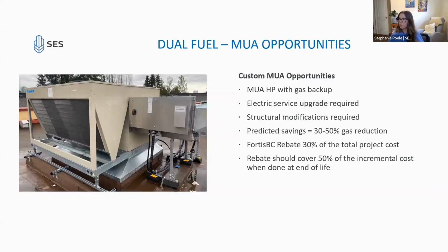Next slide. Perfect. So again, the opportunity here is a makeup air heat pump with gas backup. The caveat here is that a makeup air unit heat pump is going to need to be the actual heat pump size, and even the gas backup size is going to be quite a bit bigger than with a rooftop unit because it has to heat that really, really cold air. It can't mix it with the return air first. So it's much bigger, which means that often you will need structural reinforcements, which is why makeup air units are slightly harder to electrify. Now, obviously, if you already had cooling in place, maybe you don't need that upgrade. So it is dependent, but makeup air units are going to be a little bit trickier than rooftop units to electrify.